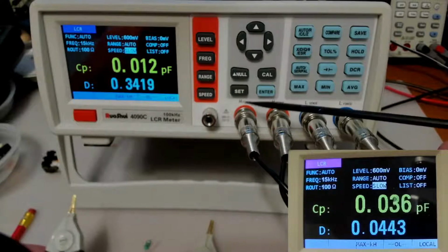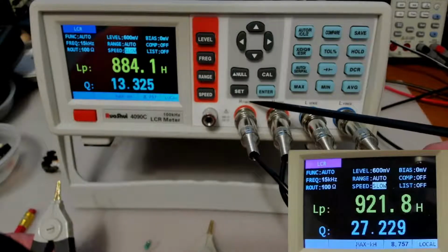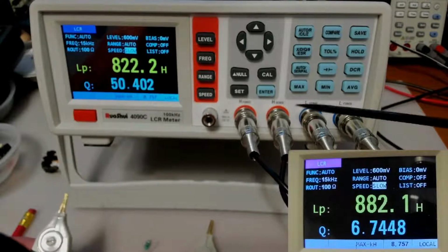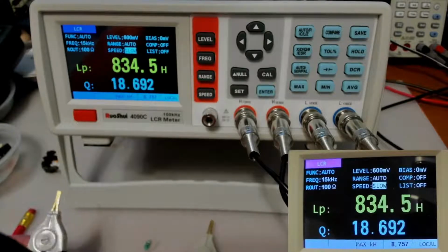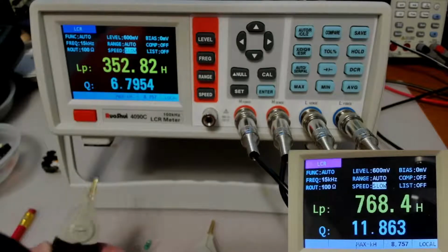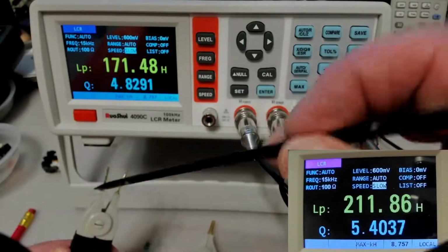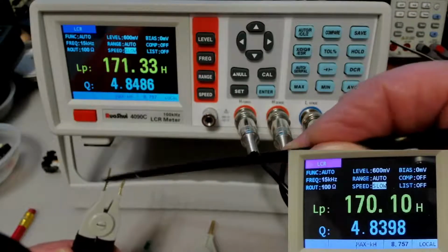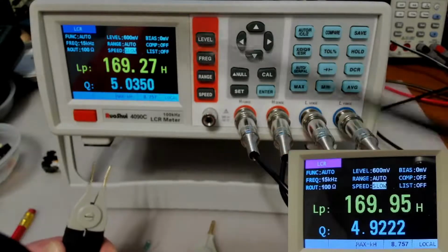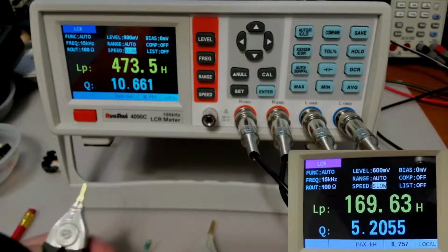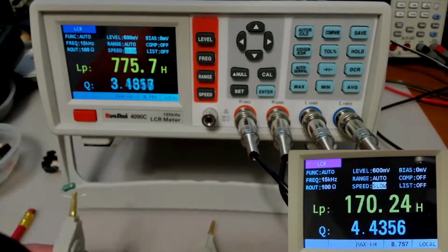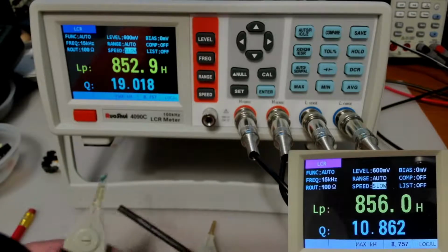One of those, like this one here, is marked H-force and H-sense, and same with this one. So what they do is there are these Kelvin clips. One of those is connected to one side of the tips, and the other is connected to the other side of the tips. Then when you grab something with it, of course, they connect together like that.